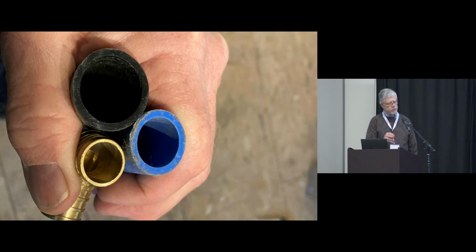If you manifold 3, and in this case it was just 2, but like in the dryer loop, 3 3/4 inch lines, if you manifold them together, you should step up to 1.25 inches. If you're using poly fittings at that point, I would say 1.5 inches to get the same kind of diameter that you would with the geothermal fittings. So that's something to take note of. I don't think it was a serious problem.